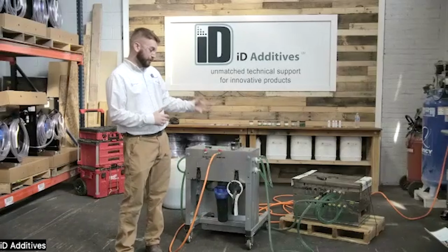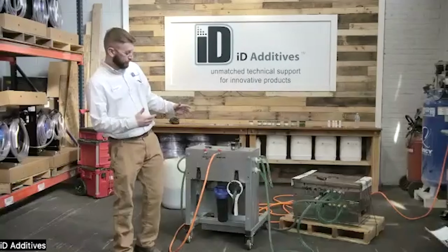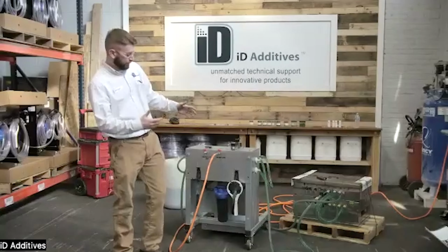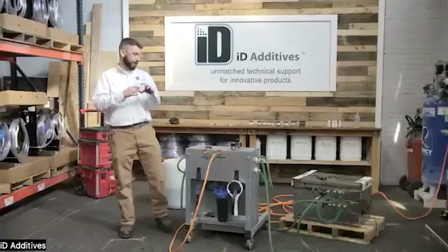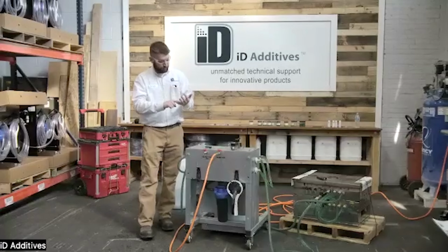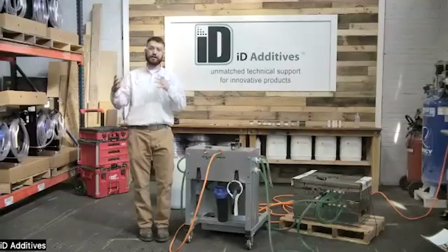In this instance, if I've jumped half the mold and I'm taking my readings there, I need to document that I did lines 1, 2, 5, and 6. So the next time it comes on the bench, if I'm reading 6 GPMs but another tech jumps lines 1 through 4, he'll think it's not the same. Make sure you're doing the same thing - that's probably the biggest thing, just document and write it down in the notebook. If you don't have the software, fine, but if you have the software, even better.